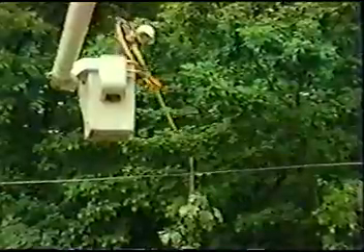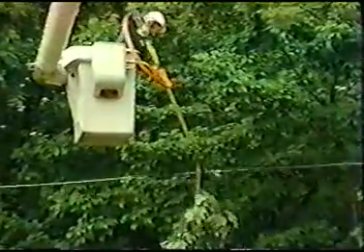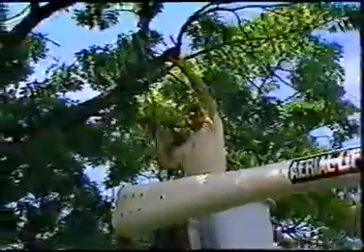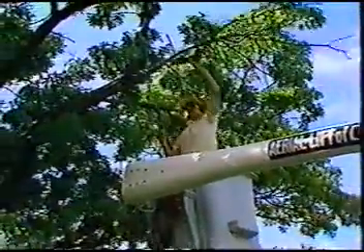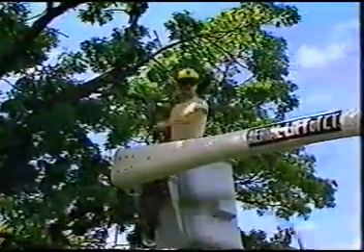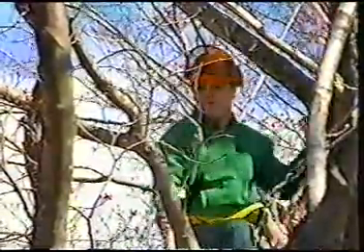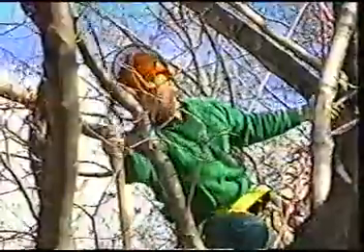Never touch a hanger lodged on a conductor except with a non-conductive tool. If you are holding a limb while cutting it, be sure that when the cut is complete, the limb will not contact the conductors. Never cut any limb unless you are absolutely sure that you can safely control the direction of fall. Pole saws and pruners should be hung on limbs, never on conductors.